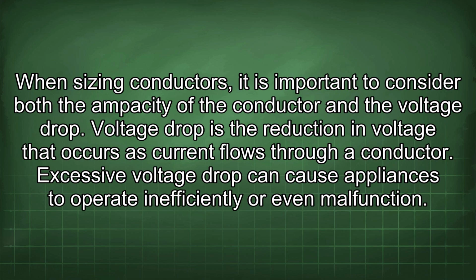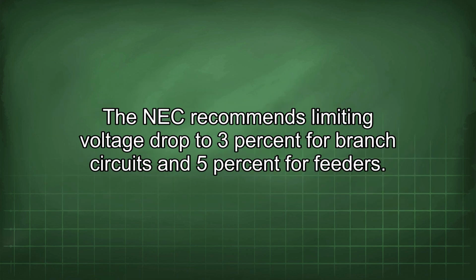When sizing conductors, it is important to consider both the ampacity of the conductor and the voltage drop. Voltage drop is the reduction in voltage that occurs as current flows through a conductor. Excessive voltage drop can cause appliances to operate inefficiently or even malfunction. The NEC recommends limiting voltage drop to 3% for branch circuits and 5% for feeders.